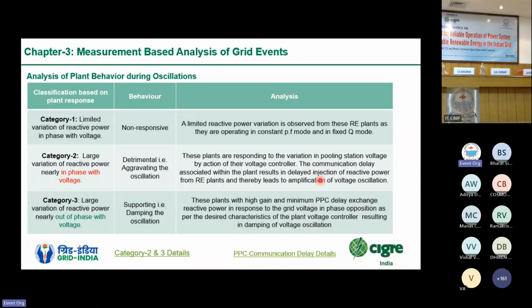So again, during the analysis of the oscillations, we were able to pinpoint to an extent that the voltage controls which are implemented in the RE plants are not helping us to achieve the desired stable voltage profile. So we have categorized the performance of the RE plants into 3 categories. Category 1 mentions that some plants which were already in the constant power factor mode appeared as if they are non-responsive to the oscillations. Certainly, they were providing limited reactive power variations, and since they were operating in fixed power factor, it is very difficult to observe any variation from them during the changing voltage scenario.